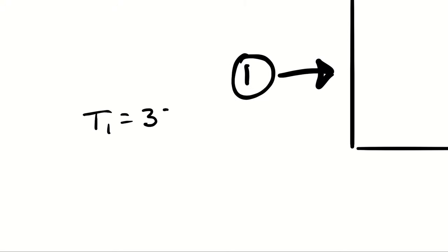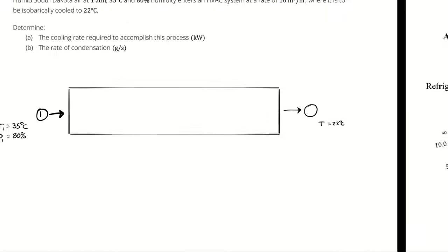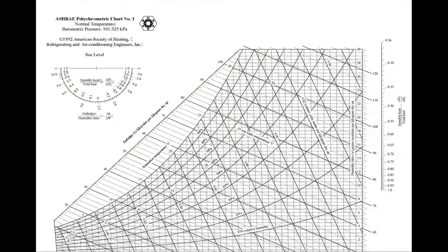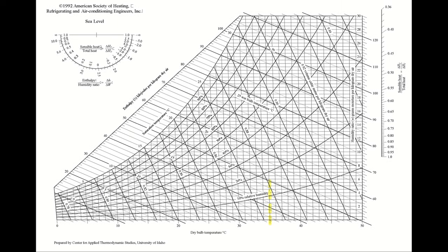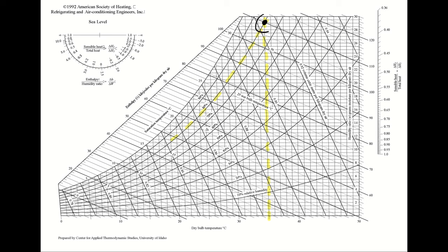So I have air entering at 35 degrees Celsius and 80% relative humidity and being cooled to 22 degrees Celsius. The first question I have to answer is: is this simple cooling or not? To answer that, let's look at this on the chart. We're starting with 35 degrees Celsius and 80% relative humidity. Those intersect up here, and my cooling process begins by moving to the left horizontally until it reaches the 100% relative humidity line. If I encounter the desired set point temperature first, then I have simple cooling.